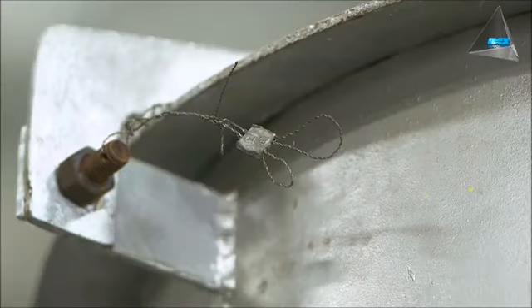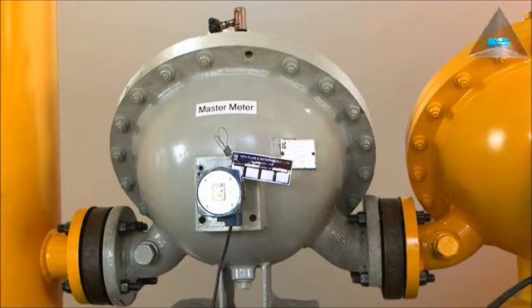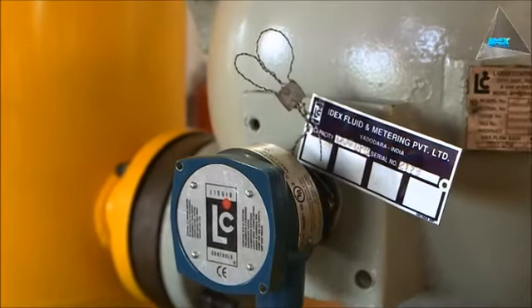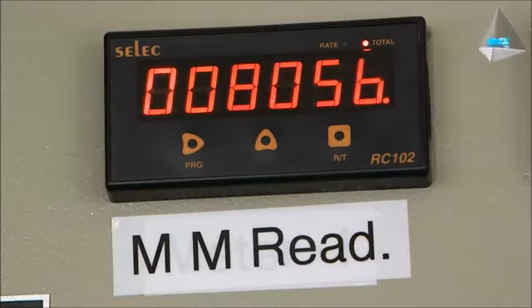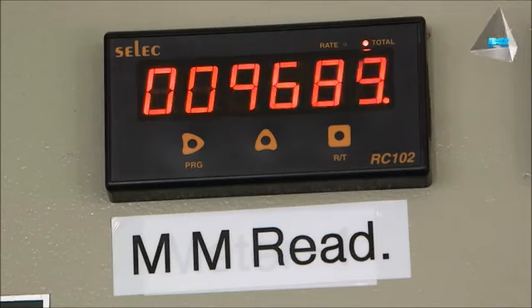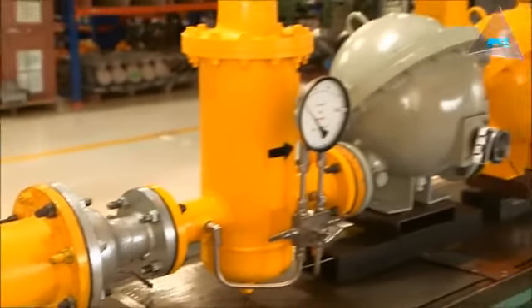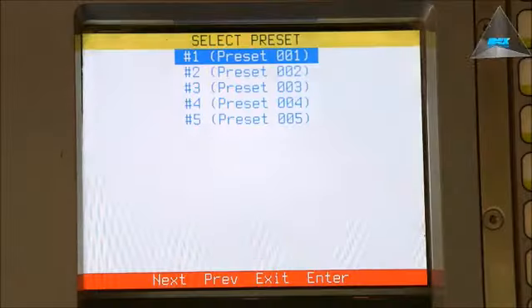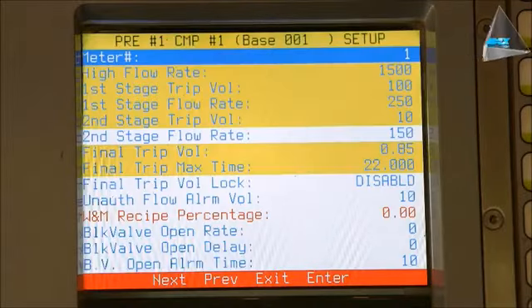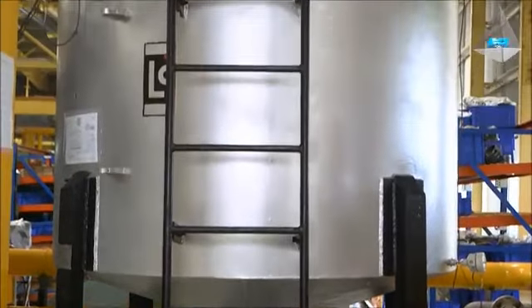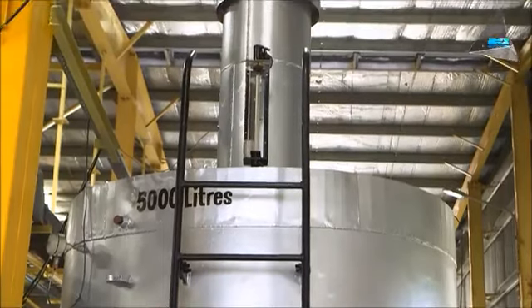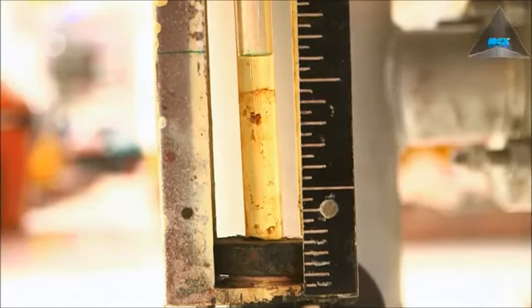the statutory authority. The master meter with LC pulse output device model POD and the electronic counter with indications of rate of flow and total will be installed along with the LC master meter on the IDEX fluid and metering test bench. A flow rate of 1500 LPM will be set using the master meter and the prover will be filled completely to wet for 10 minutes.